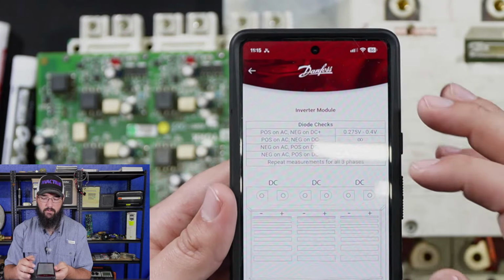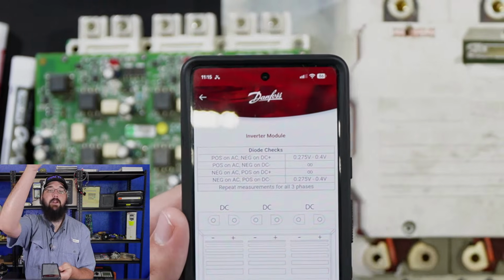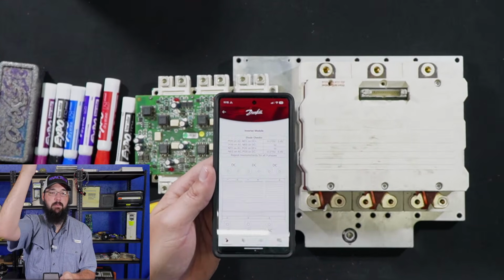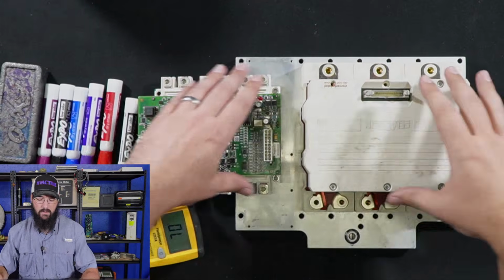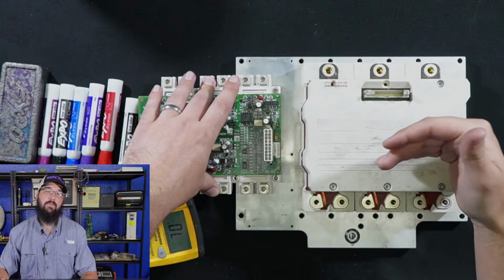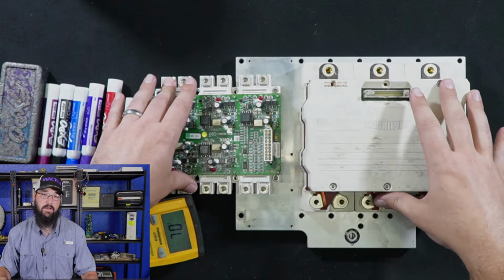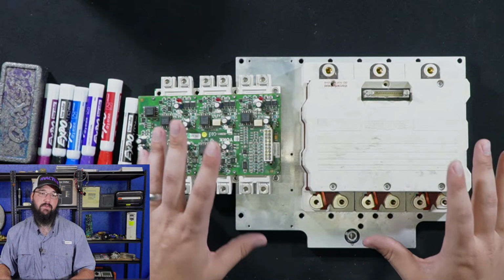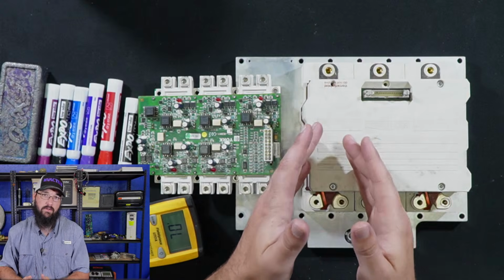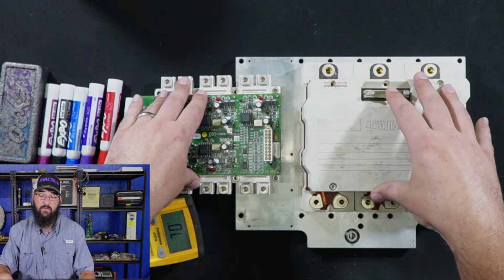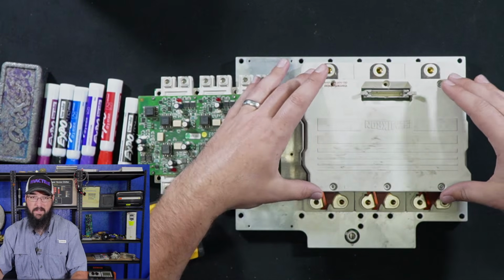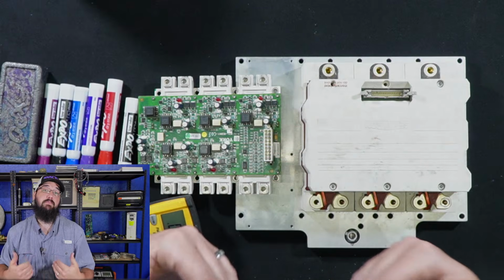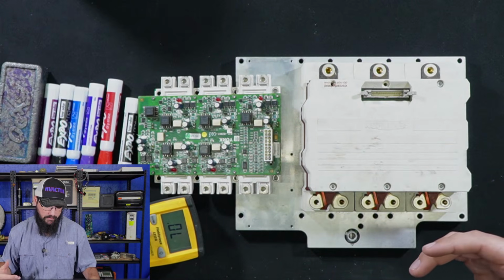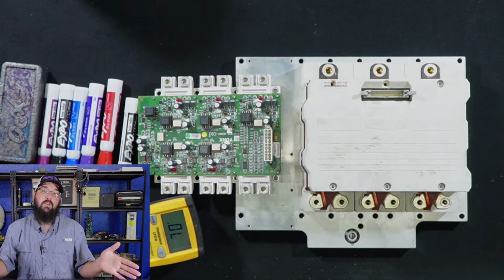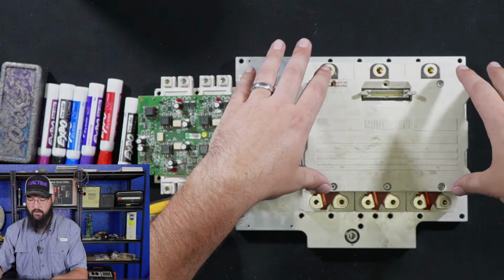So just to kind of show you, now these are very generous numbers. Okay, I can say from my background and my experience, usually I want to see between 0.36 to 0.38 is what a lot of these will measure at. Now, most of the manufacturers will say that technically, as long as you're within 0.3 to 0.4 VDC, you're considered good. Now, the particular one that Danfoss is using is actually saying, hey, as long as you're within 0.275, which I think is quite generous. For me, by the time I'm getting that close to the edges, I start to get fairly nervous, right? So this one being 0.31, it's considered good.